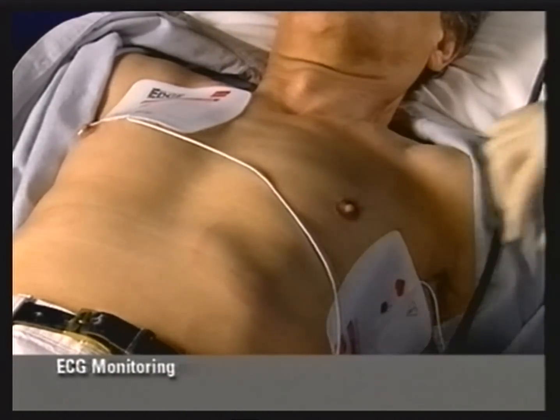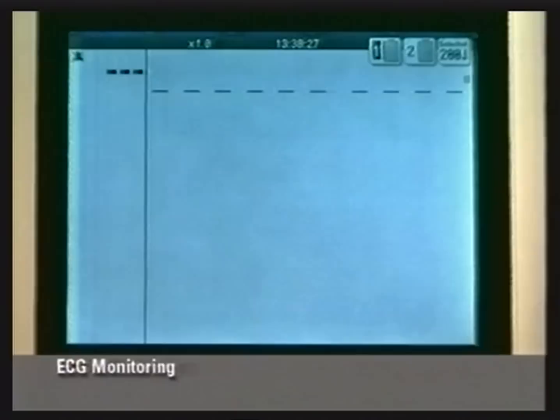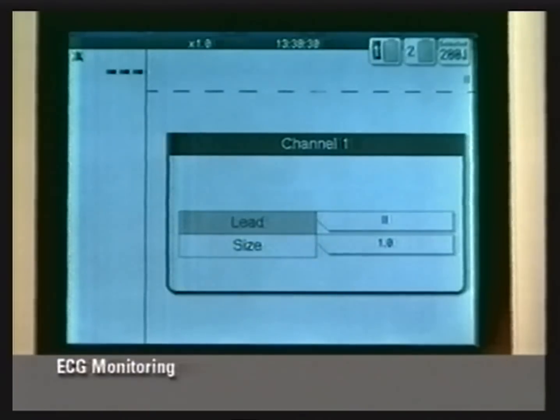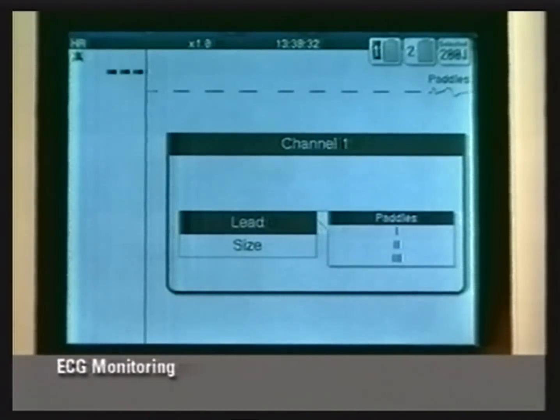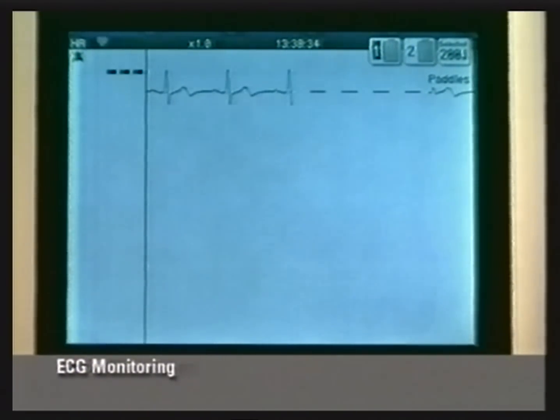Check that the ECG is displayed on the screen. If the power on default for the ECG is lead 2, select paddles lead. As previously described, check the ECG size and that heart rate counting is correct.